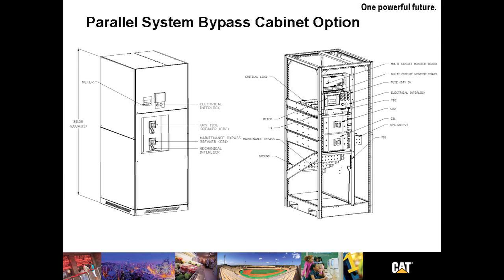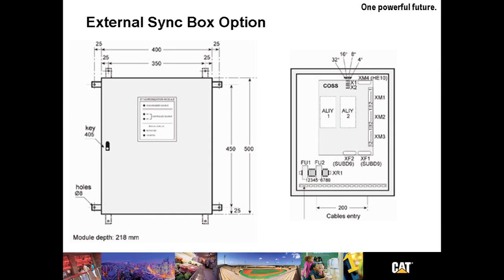The external sync box option provides for connections to synchronize the output of the UPS through the inverter to an external source or UPS. Typically one box is required per synchronized system. It provides for connections in the UPS to communicate with the external sync box for synchronizing to the external source or UPS, and requires one board per UPS being synchronized. Interestingly enough, this sync box option can sync to other UPSs, gensets, or even the utility.